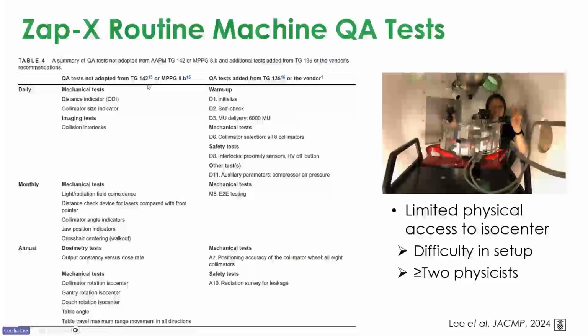We actually followed TG-142, thoroughly reviewing what we can adopt and what we cannot adopt, because the machine has different characteristics, so certain tests we couldn't adopt. For example, the machine doesn't have ODI, so we cannot perform that test, and it doesn't have a light field, so we cannot perform that test. I listed all the tests we couldn't adopt, and on the right, what else we had to adopt. Mainly, I looked up the CyberKnife task group report, so we adopted from there, and there was also some early vendor publication. So I looked those up and implemented them.